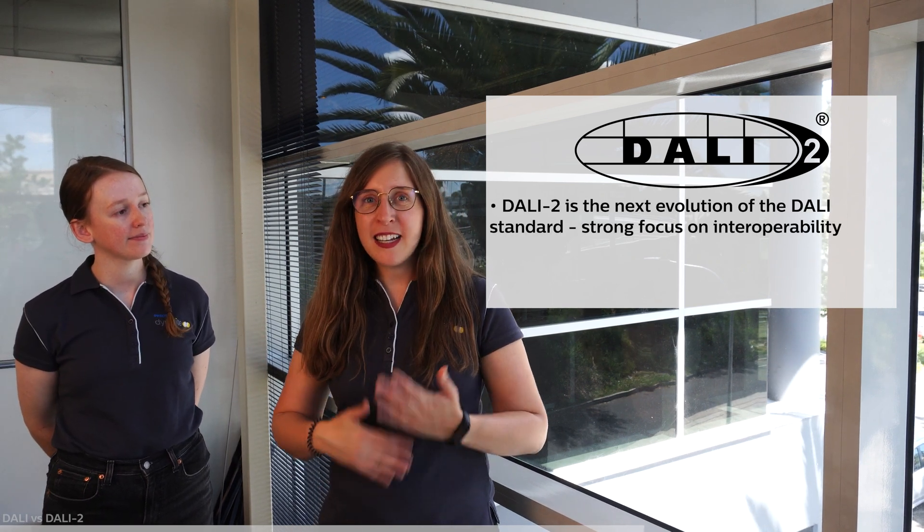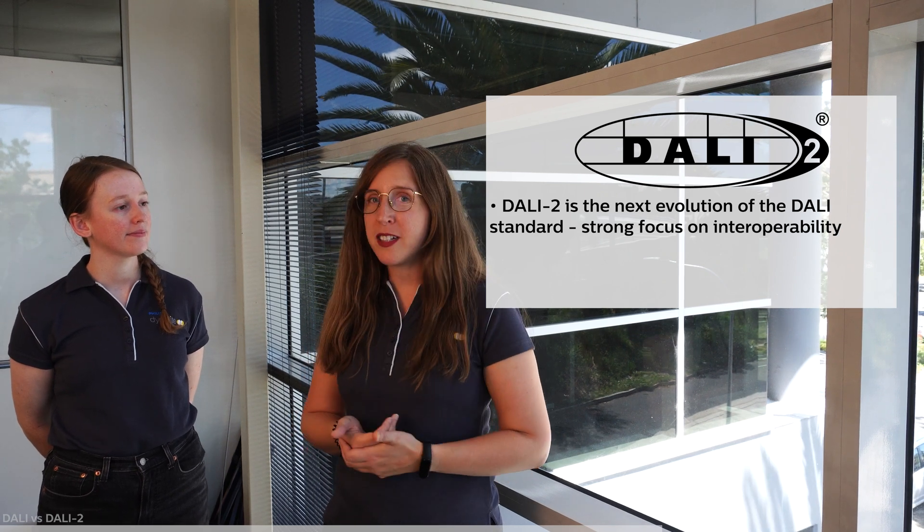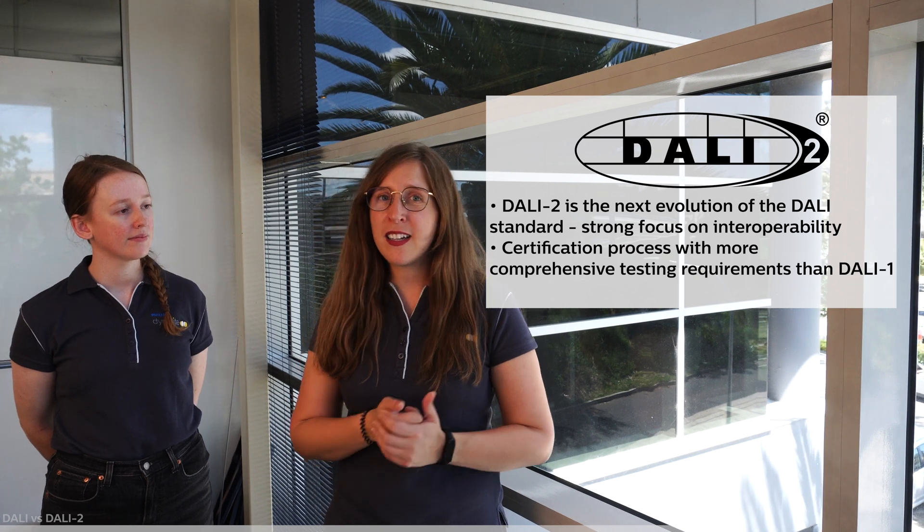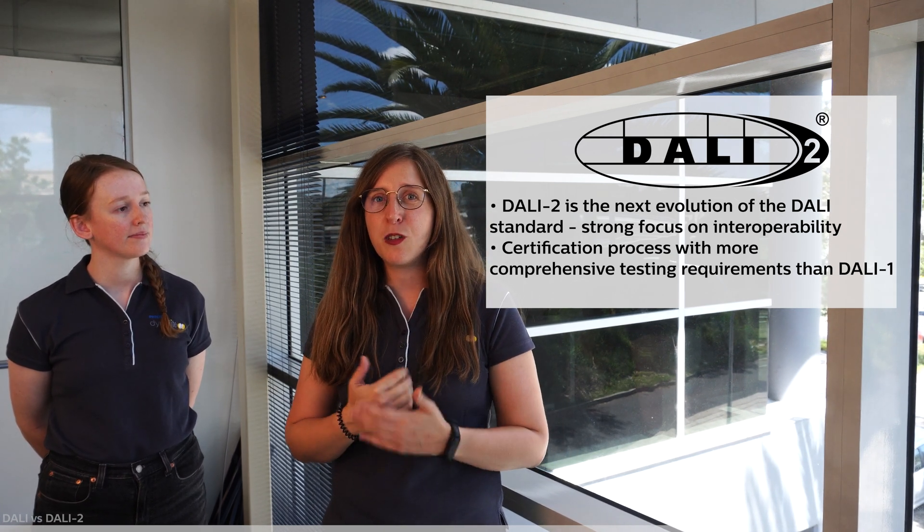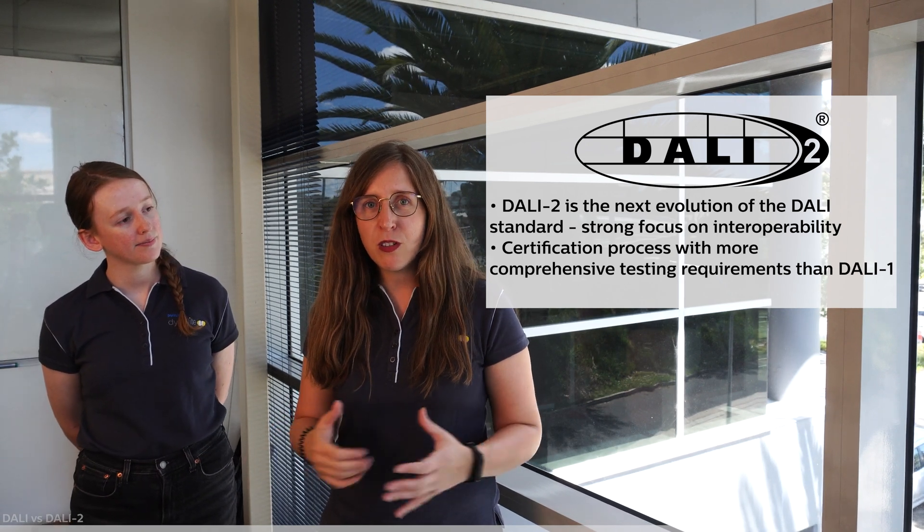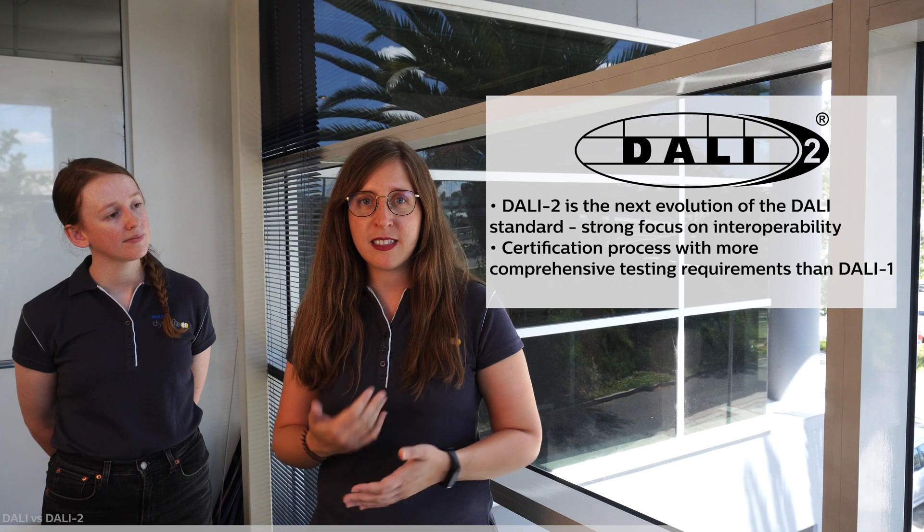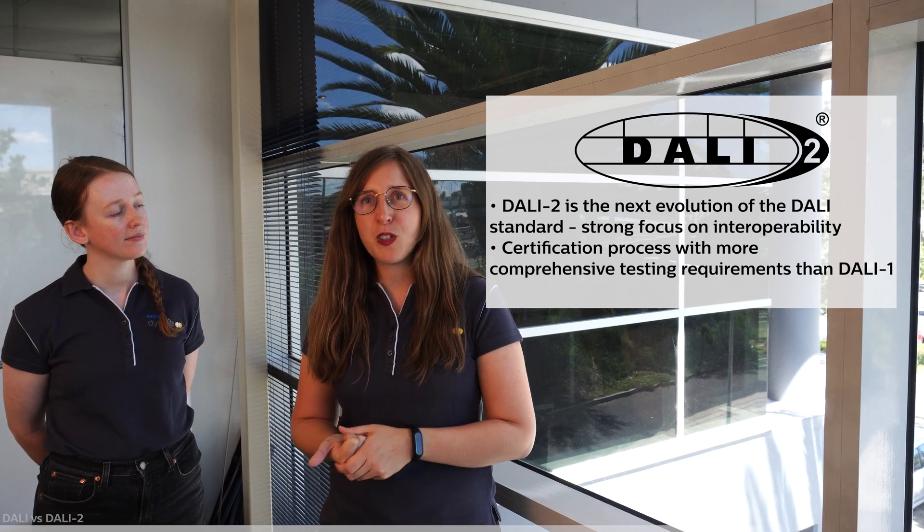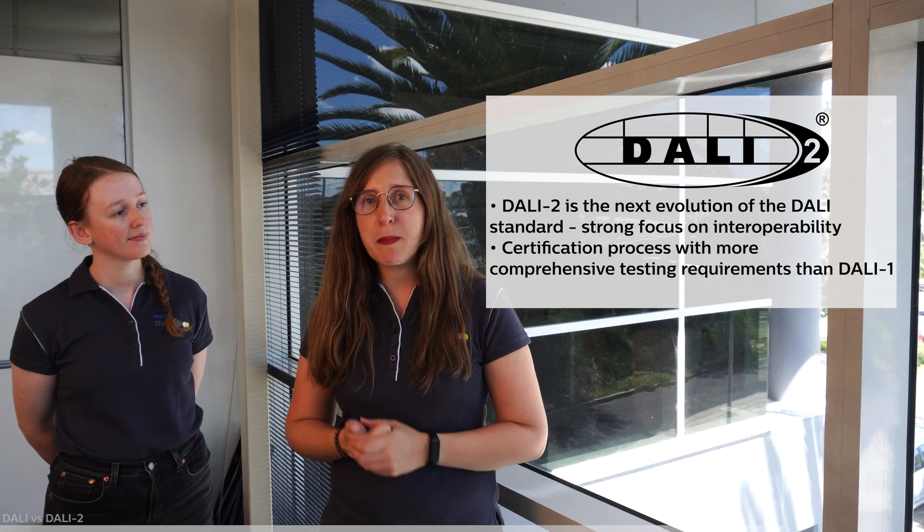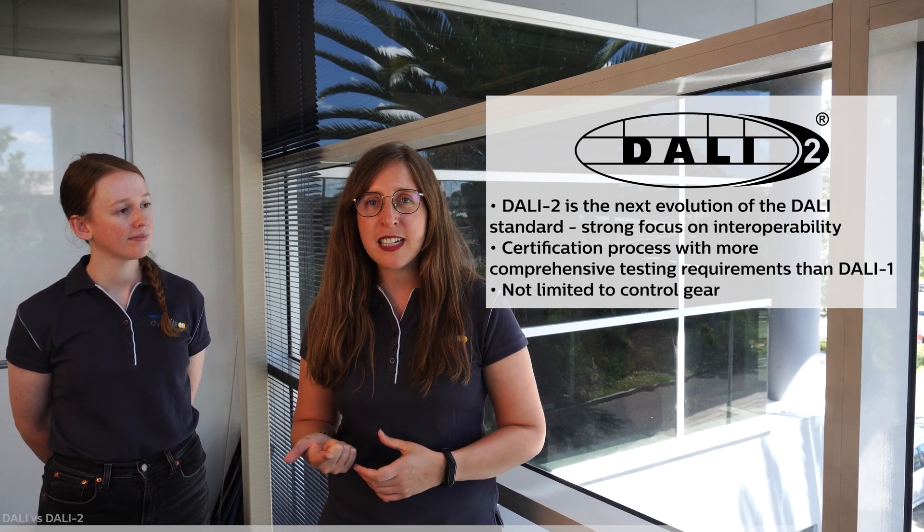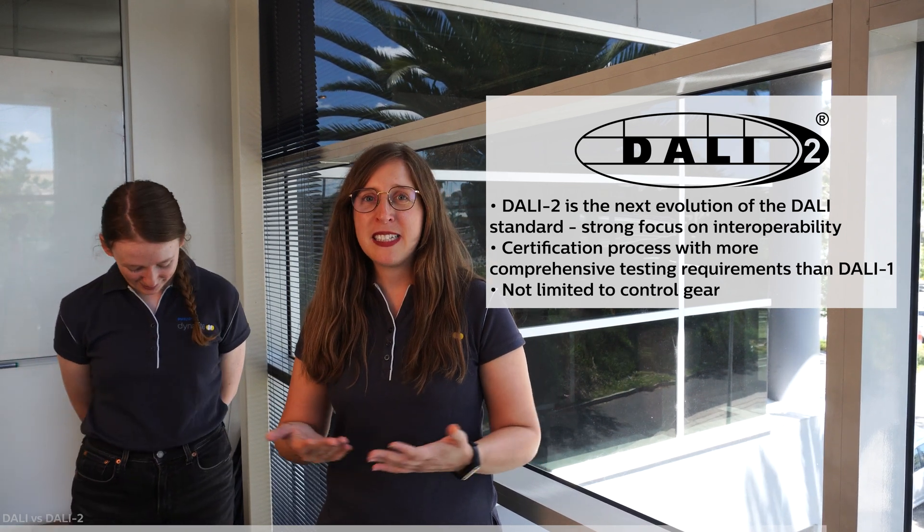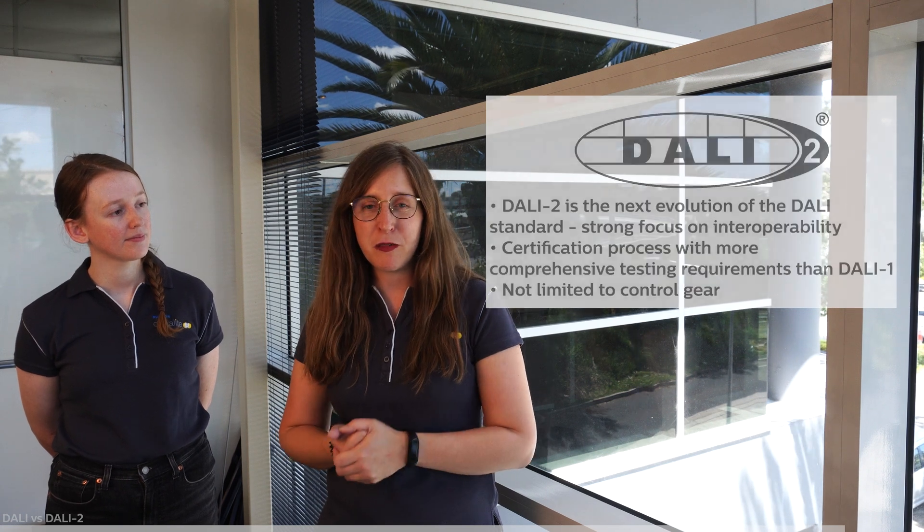So is it fair to assume then that DALI 2 just builds upon the principles of DALI 1? Yes, but DALI has been constantly evolving so it's not only a new version but we want to remark here that it's also a certification process. So unlike DALI version 1 where each manufacturer certifies their own products, now DALI version 2 established a protocol or a test, some more detailed tests to certify not only the LED modules or the DALI bus or the drivers but also the application controllers, the input devices such as for example sensors or even the power supply.